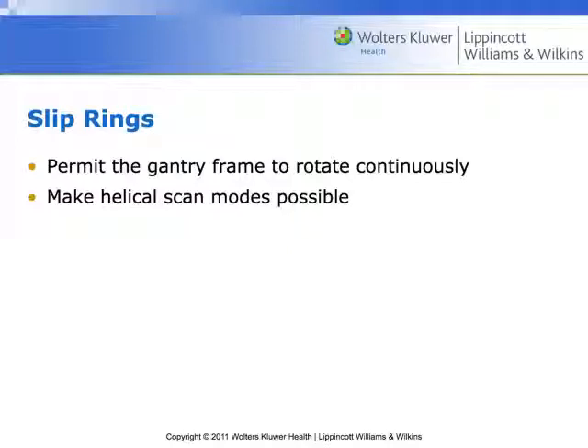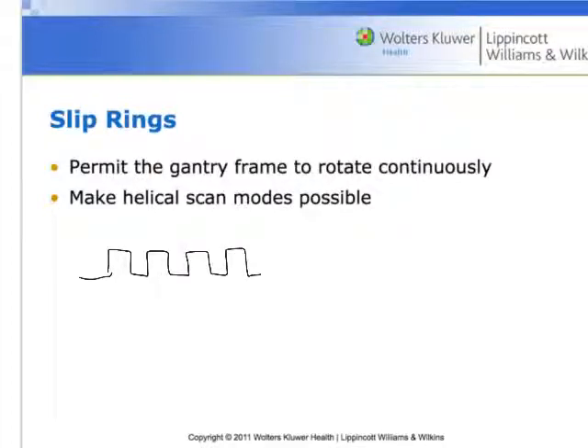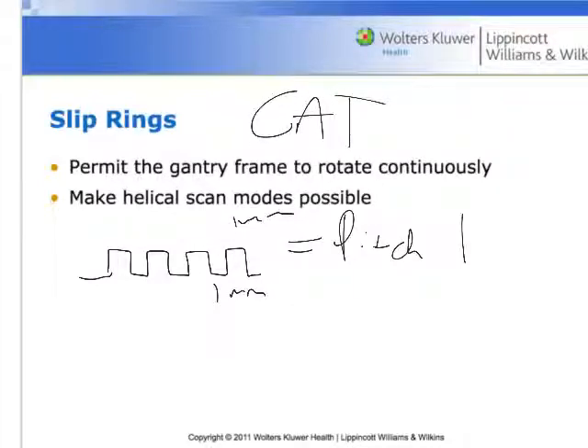In axial scanning, the table moves, then we scan; the table moves, then we scan. If we have a pitch of one, the movement equals the scanning thickness — for example, a one-millimeter slice thickness matched with a one-millimeter movement. Move, scan. Move, scan. That's axial scanning, which is what we were referring to as Computed Axial Tomography.